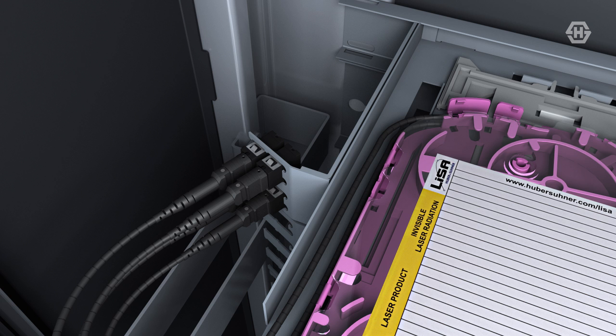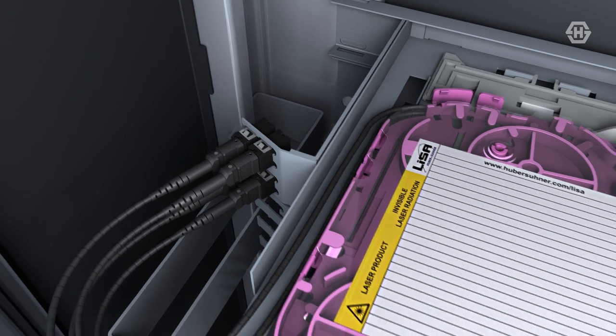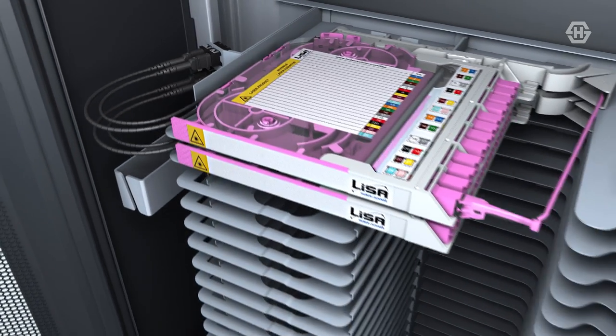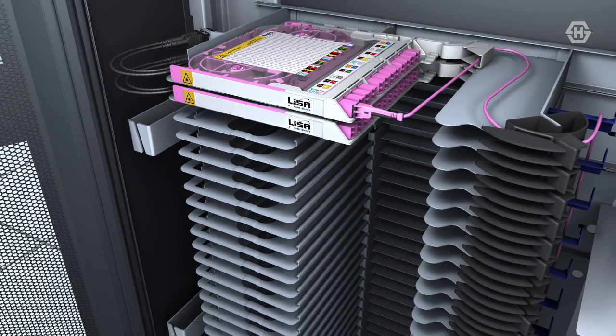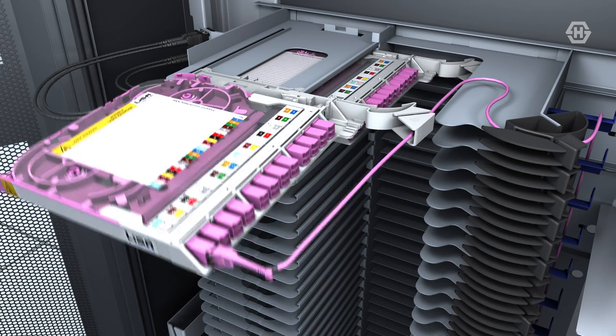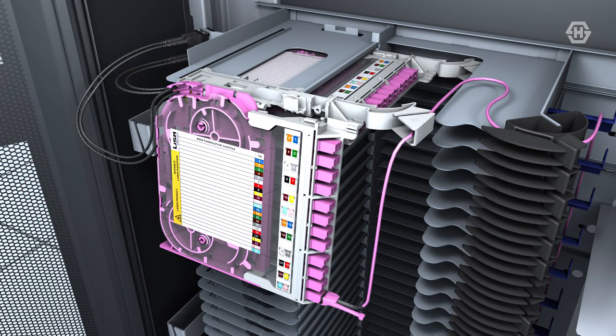This open-sided concept allows cables to be added or removed at any time without the need to route them through closed holes. The main purpose of this secondary fixing point is to maintain a service loop of cable so that Lisa fiber trays can be inserted and removed at any time during the lifetime of the system. Sufficient service loop is afforded so that the Lisa fiber tray can be slid out from the tray unit and hinged down to its fully open position.